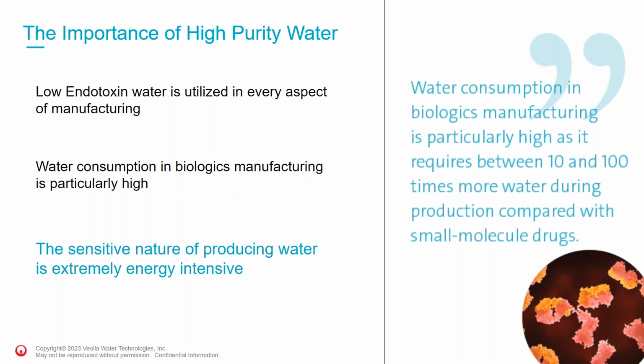And as we say on the right-hand side there, water consumption for these sort of manufacturing sites requires between 10 to 100 times more water during production compared to small molecular drugs. And also the quality has to be maintained no matter what the volume you're using. So quality is important because the products are sensitive in nature to the changes in that product quality. So we must maintain that quality in terms of meeting those USP or European Pharmacopoeia specs for purified or WFI water.